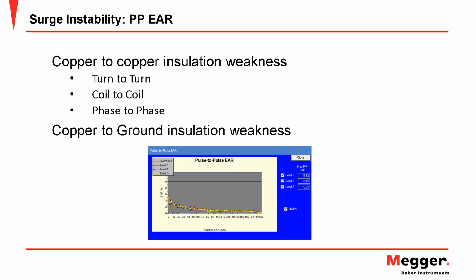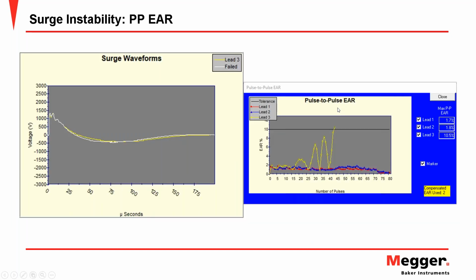Surge testing is also evaluating copper to ground to some extent. It's not the entire winding, but just that front end. But we use this pulse-to-pulse EAR graph as a tool, for any spikes that we see in this graph would be indicative of insulation weakness in these particular locations.